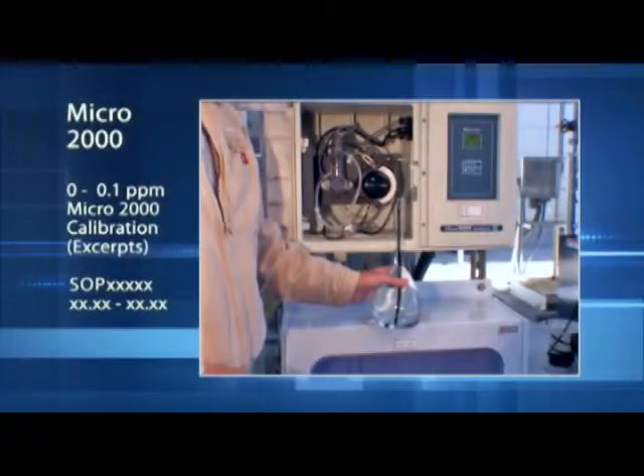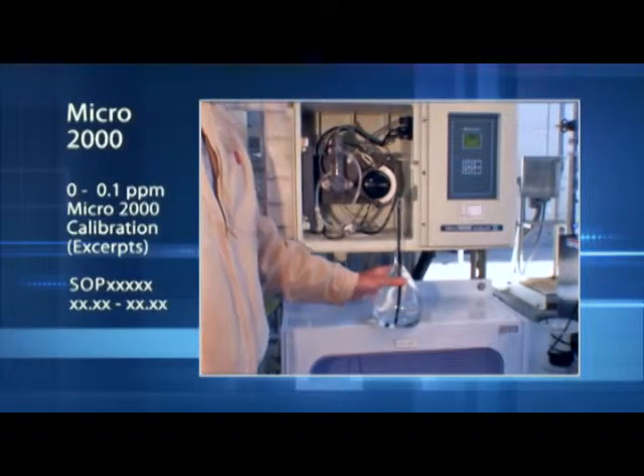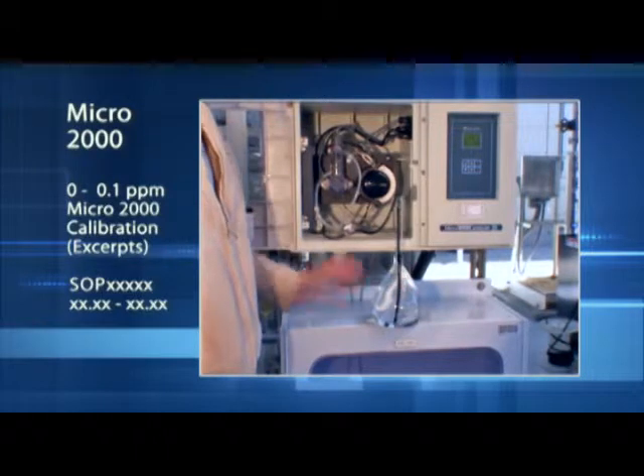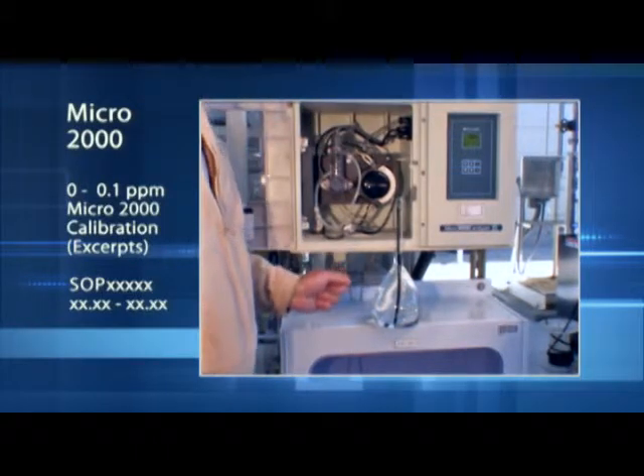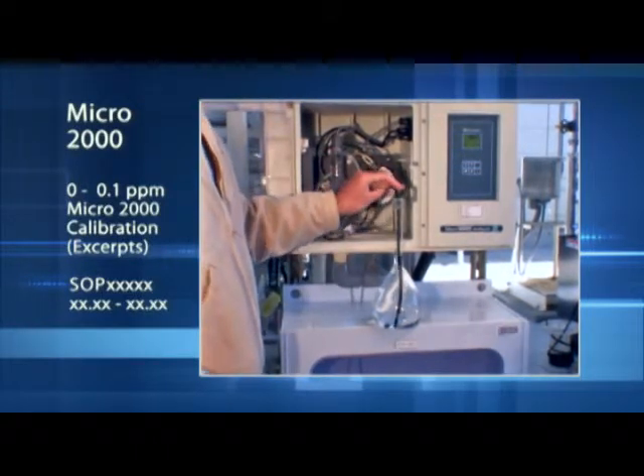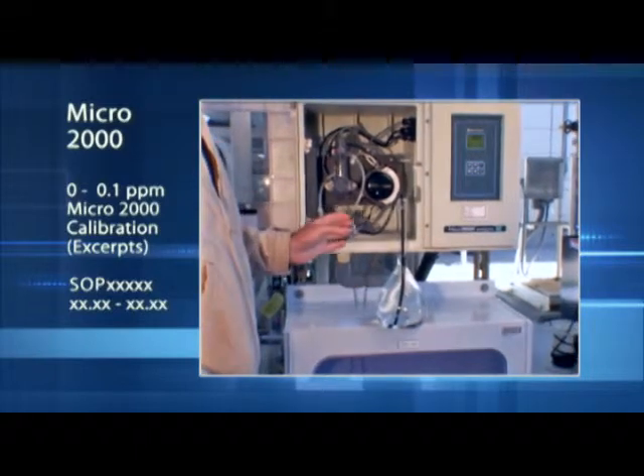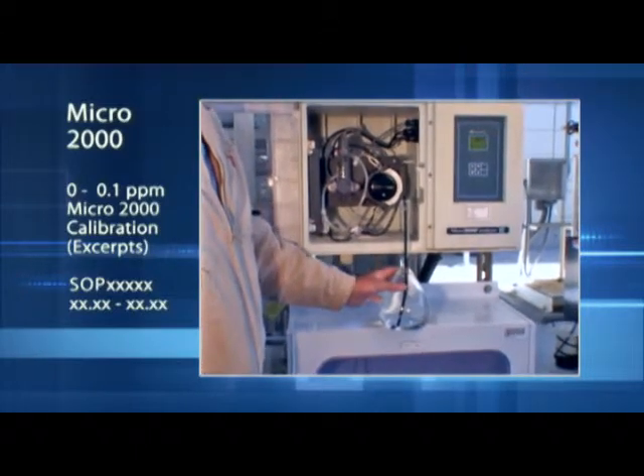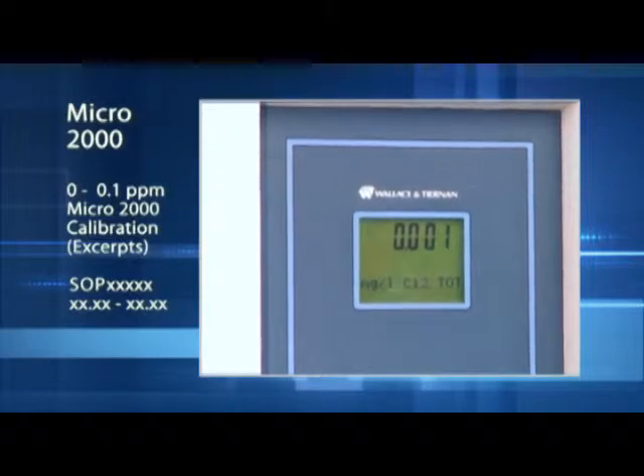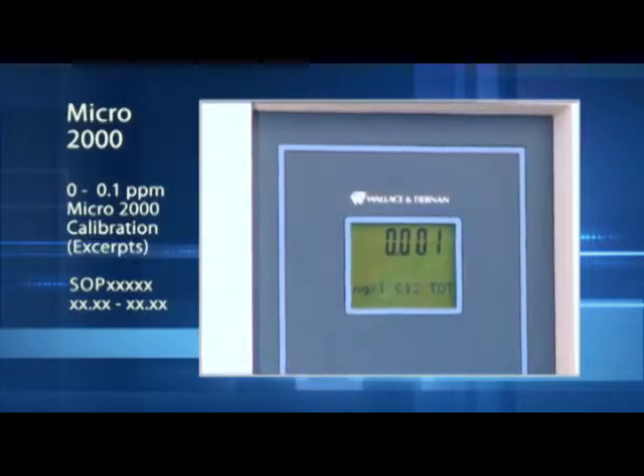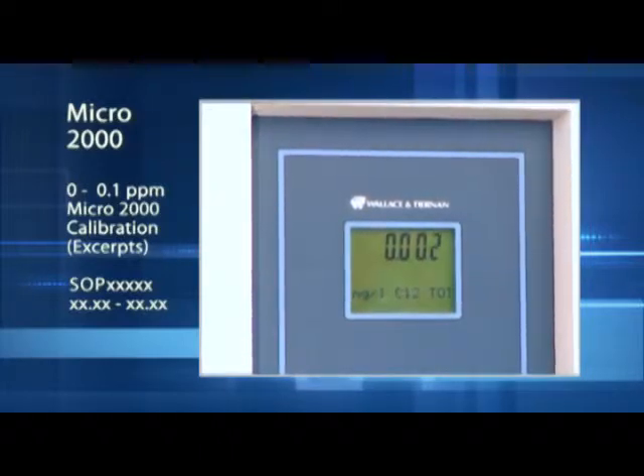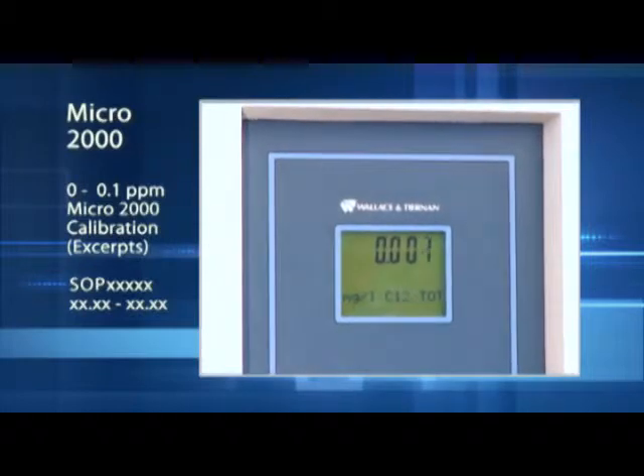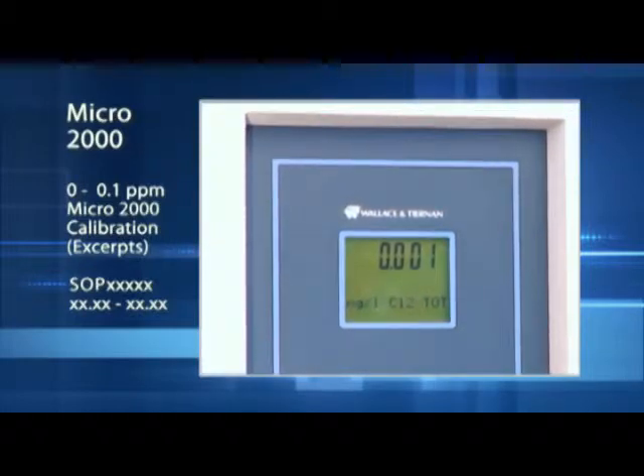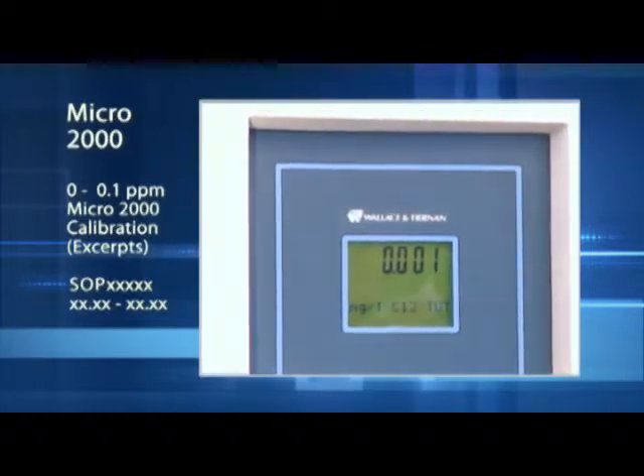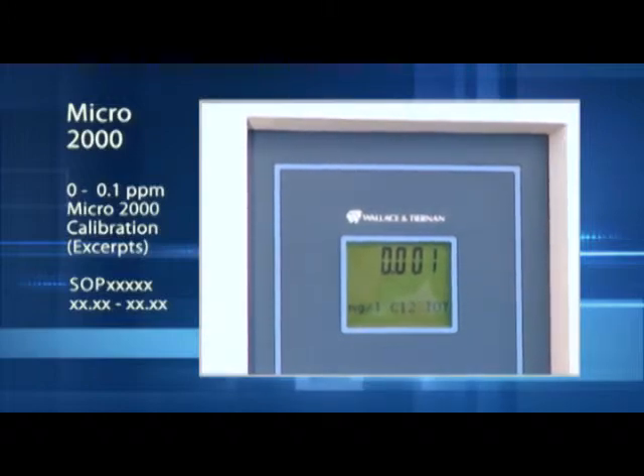So we've made a second solution to verify the original solution, which didn't quite match what the readout was. So we've put the calibration tube inside the flask and now pulling a suction off of the flask. We will now wait 10 to 15 minutes for the reading on the display to stabilize, and we'll match that reading with the known reading of the flask and adjust the calibration as necessary.